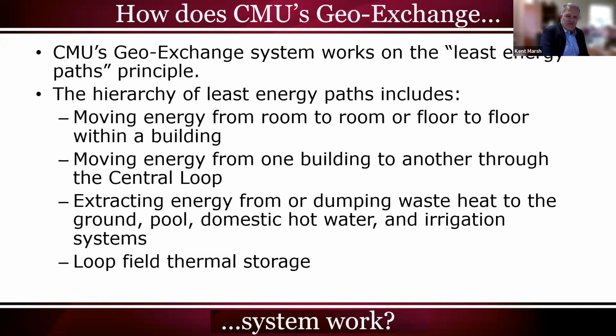The third least energy path is when we've extracted more heat, or added too much heat, to the central loop, and now need to dump that waste heat into, say, our swimming pool or a domestic hot water system on campus, or move it into the ground. Likewise, we could need to move heat from the ground into our central loop. Those are the basic paths we use to turn pumps on throughout campus to move heat between our various resources and assets.